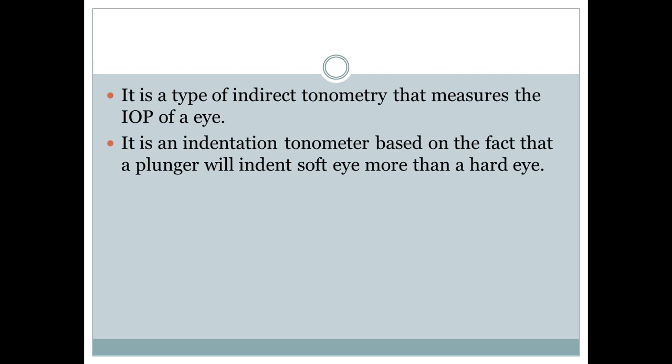This is measured mainly by measuring the depth produced on the surface of the cornea by a load of a known weight. It is based on the fact that the plunger will indent a soft eye more than a hard eye. This means that the more the plunger indents the cornea, the higher will be the scale reading and the lower will be the IOP. The indentation of corneal surface is inversely proportional to the IOP.